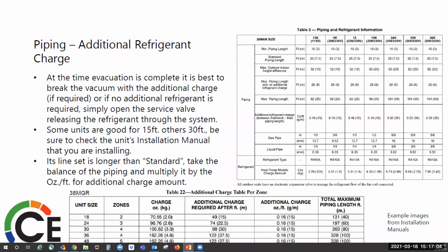You want to refer to the installation manual for how much refrigerant needs to be added to this system, if any. Take into consideration height, length of line set, you're looking for. And then when you break the vacuum, you want to use that extra refrigerant to break the vacuum with.